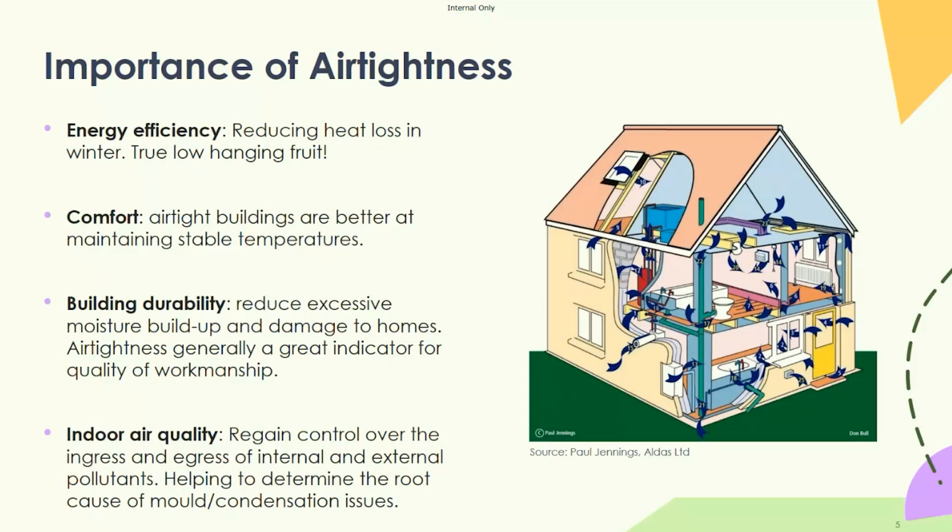And then air tightness is not strictly going to have a direct influence on indoor air quality as such. Making a property more airtight isn't going to make the air cleaner or reduce the generation of pollutants within or outside a home, but it is going to give you much better overall control. For instance, for properties near busy roads, there's a lot of external air pollutants. By being more airtight, you can then actively manage the ventilation strategy, making sure that you're pre-filtering incoming air or delivering sufficient air changes to make sure that pollutants aren't lingering in a property.